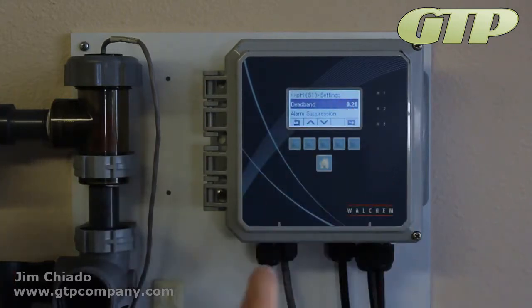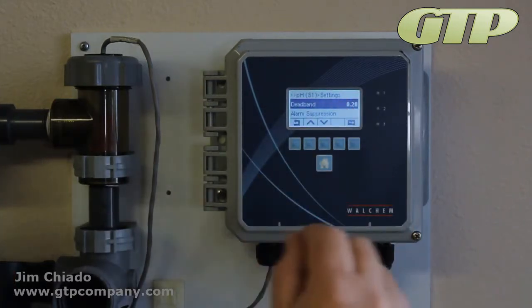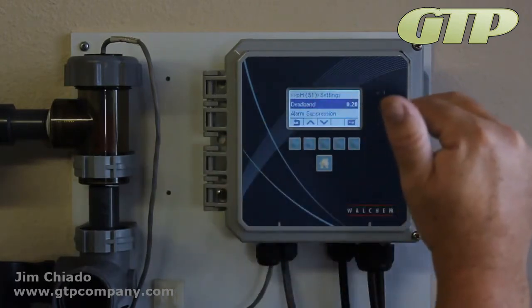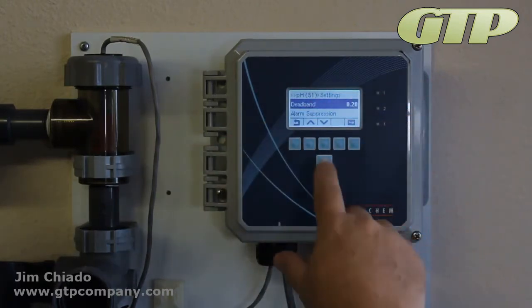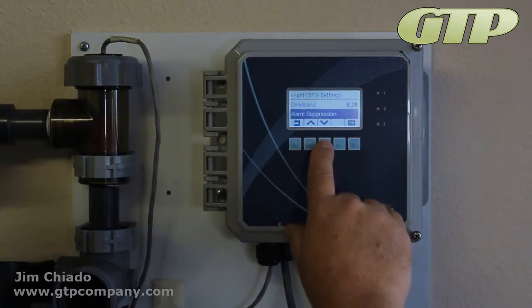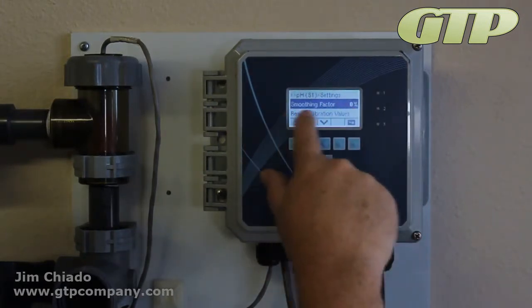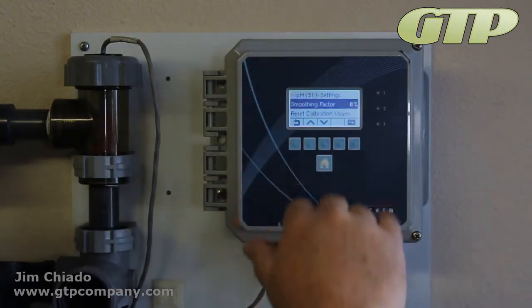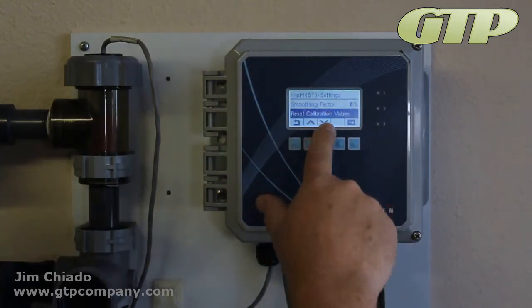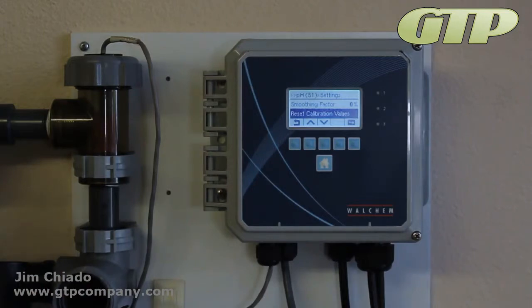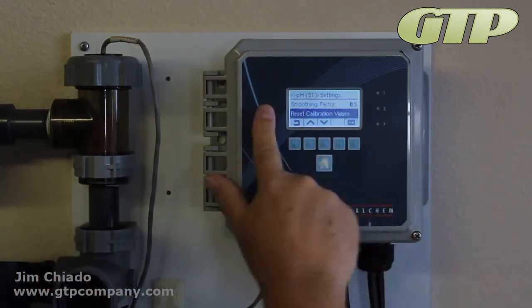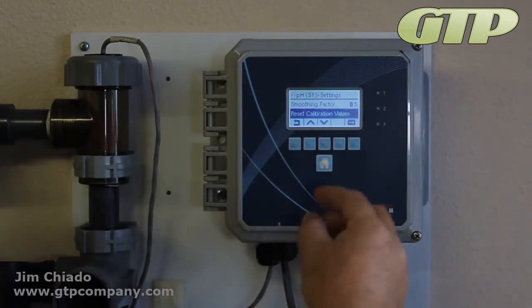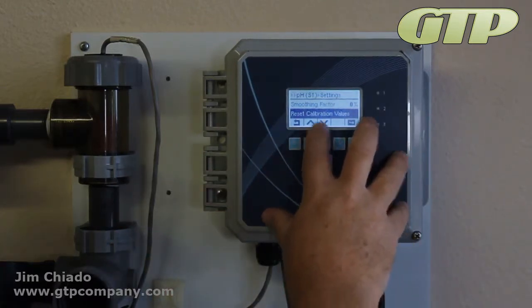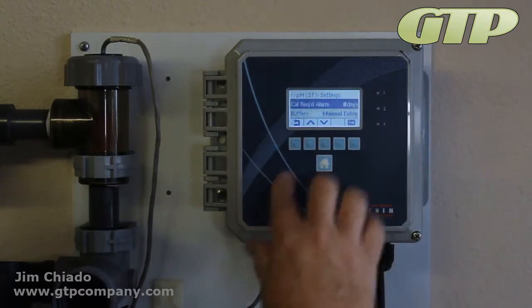Deadband, this is based on just the alarm settings. If it's 8, it'll go down to 7.8 before it actually shuts off. Alarm suppression, you can suppress it, but I wouldn't. Again, it's a nice thing to have. Smoothing factor keeps it from jumping around. Reset calibration values, just like in the conductivity version of it. You do want to reset the calibration values when you're switching out sensors, when you switch out the electrode at the bottom, and it just does start fresh again.